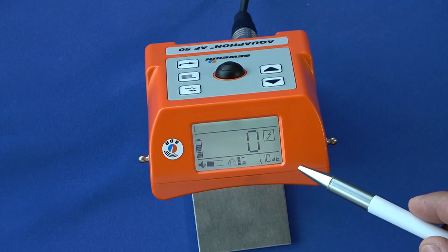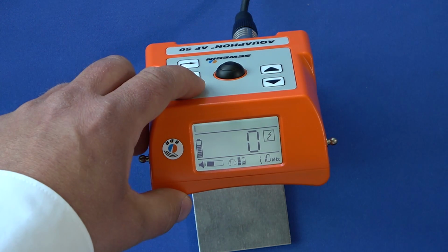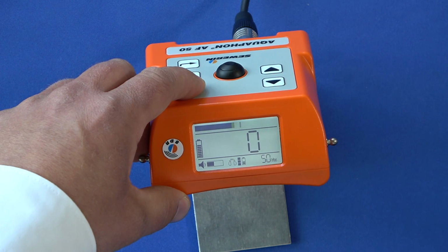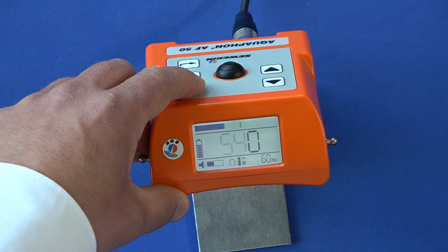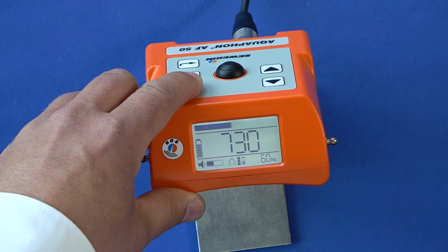At the bottom right, you see the selected location frequency, which can be changed by pressing the filter button. In addition to the 3 active transmission frequencies of the Ferrophone FG50, 2 other frequencies are available. These are used for the passive location of live cables. Adapt the location frequency of the AF50 to the selected transmission frequency of the Ferrophone FG50.